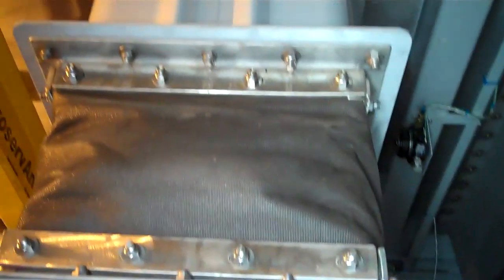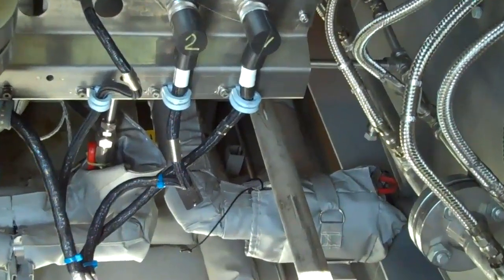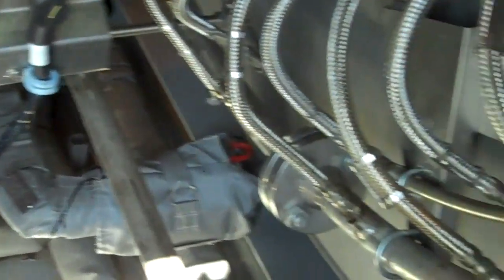When you're running the unit, the low pressure compressor and turbine goes at 3,600 RPMs. That's what's coming from your generator. The high pressure compressor and turbine operate between 8,000 and 10,000 RPMs. Part of how you change load is the speed of that high pressure compressor.